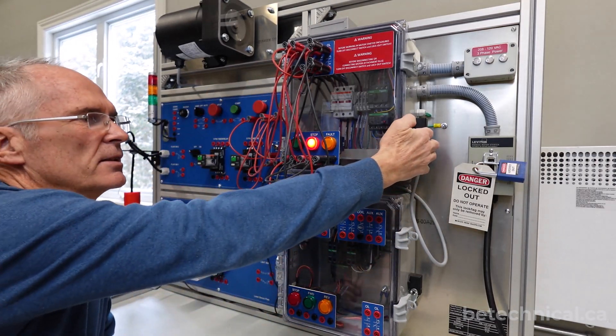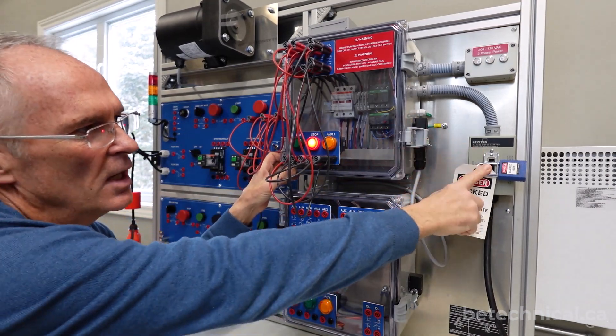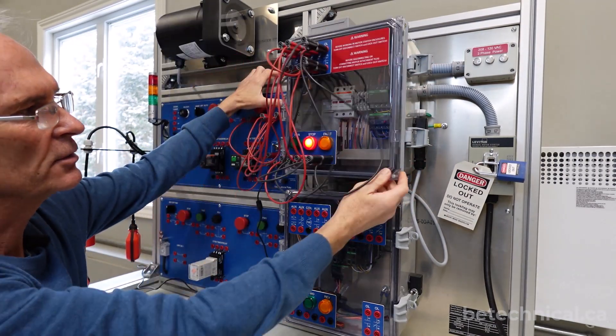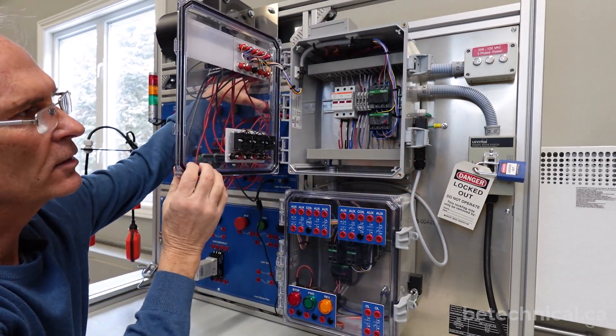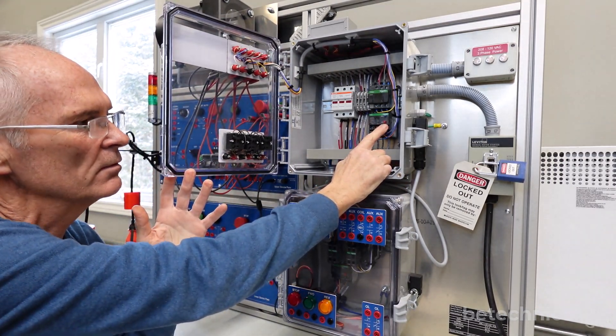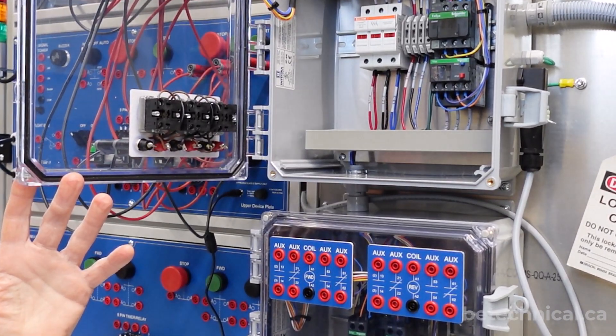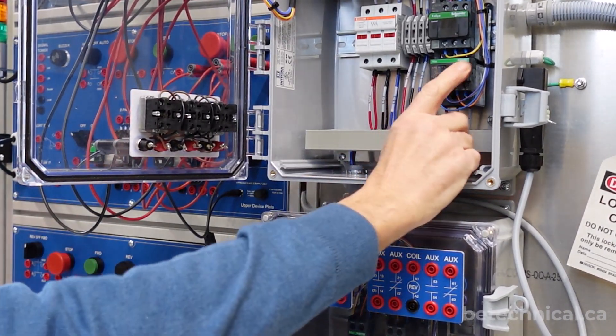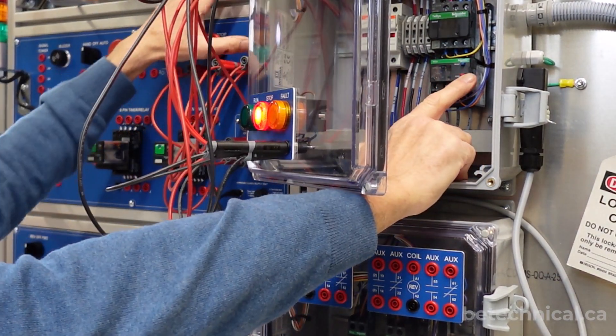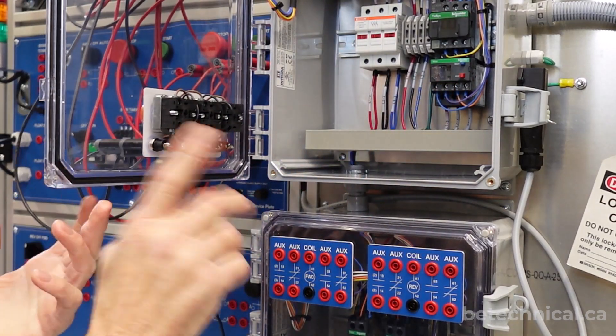And I'll test start stopping of the circuit and I'll show you how that's done. So where I'm locked out, I'm going to open the enclosure. I'll open the enclosure, I'll set it to run mode so you can hear that coil pulling in. And there's a stop button. I'll zoom in. So if I hit that stop button you see the coil drop out. So I'll do that again. I'll hit the start and then the stop button. So I can test stopping and it will stop a two wire also, a two wire type control circuit.